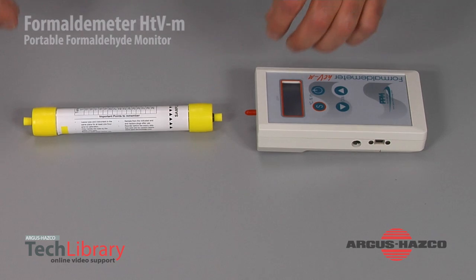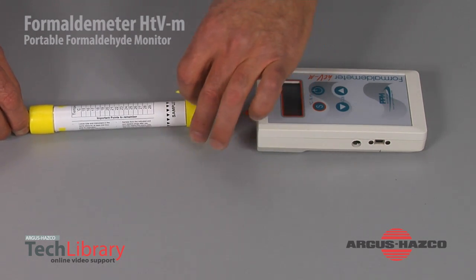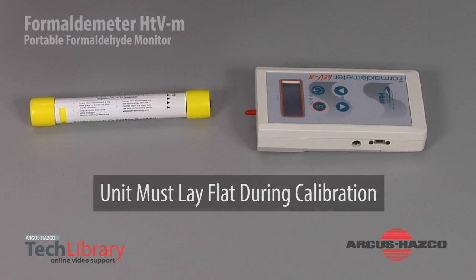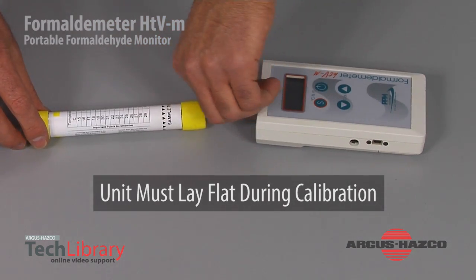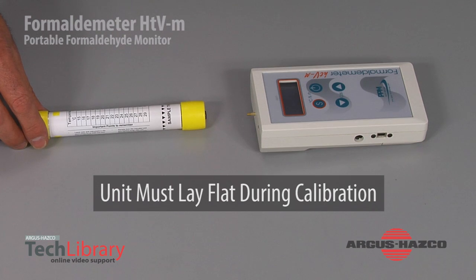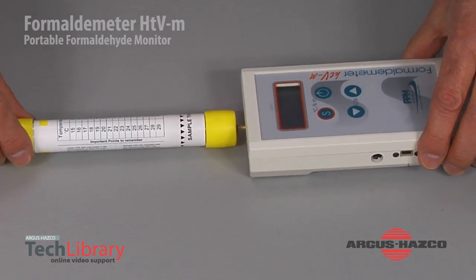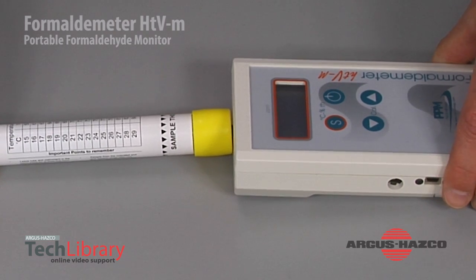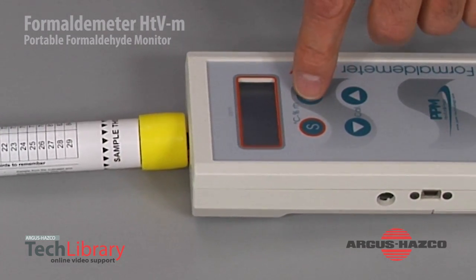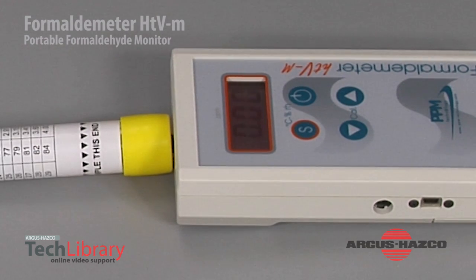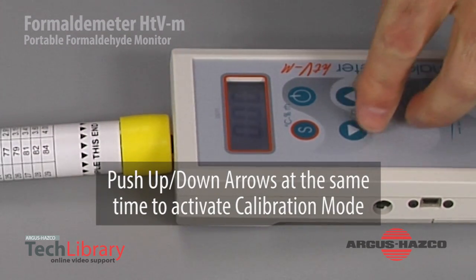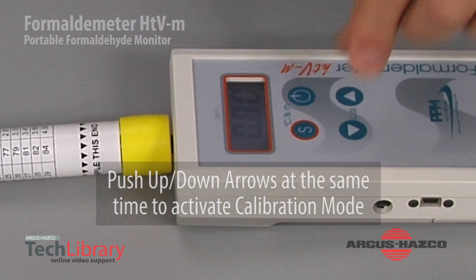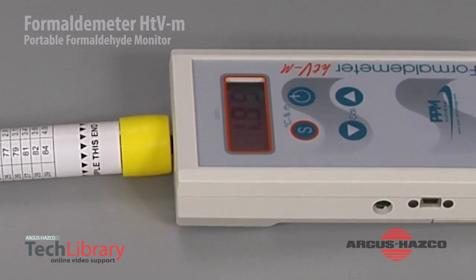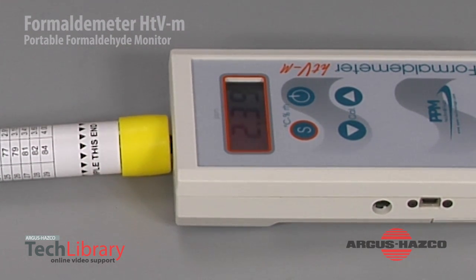At this point, you want to remove both end caps on the calibration standard, as well as removing the red cap from the instrument. Make sure you squeeze both firmly together. Turn the instrument on. Push calibrate. The instrument will count down 60 seconds. You'll see a series of numbers on the display that'll keep flashing for a period of 60 seconds.